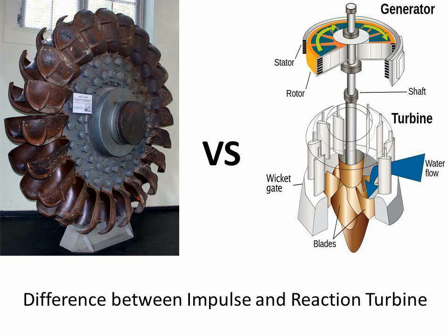Water turbines are generally divided into 2 categories: 1. Impulse turbines used for high heads of water and low flow rates, and 2. Reaction turbines normally employed for heads below about 450 meters and moderate or high flow rates.